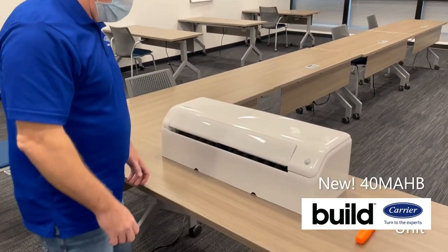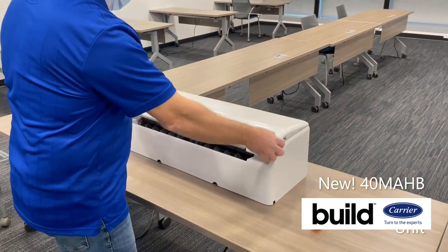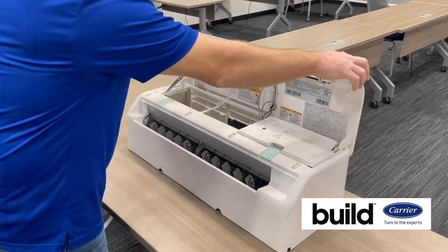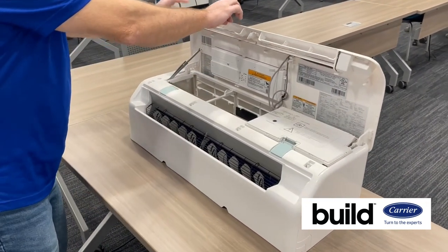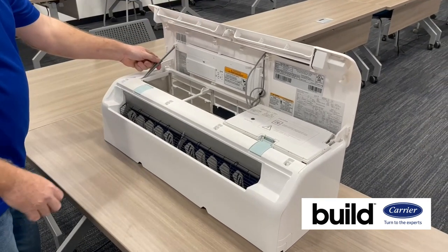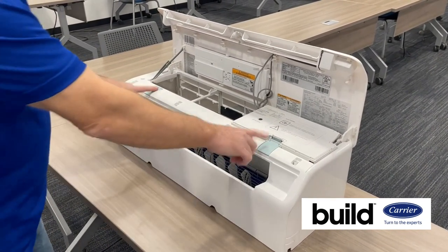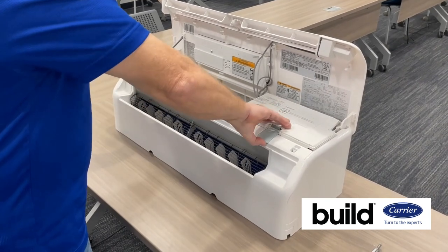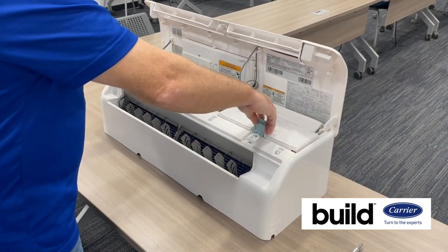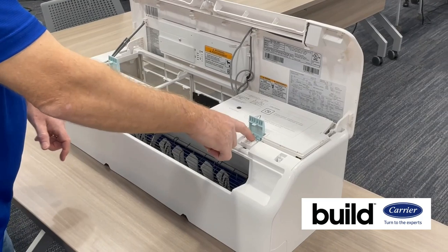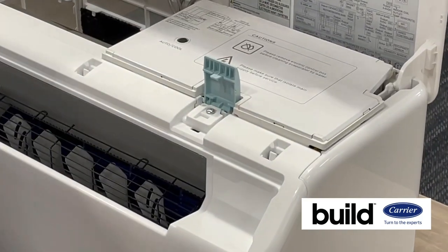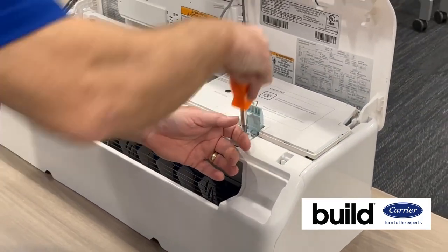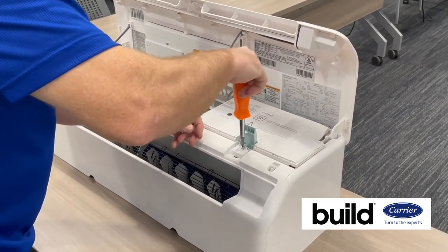Hi, this is just a quick video on how to disassemble the new Carrier mid-tier high wall unit. The first thing we want to do is hold it at each end, and then this prop rod, you position it all the way back and it will hold it up. Then you'll see you have two locking clasps right here and right here - all we want to do is take those loose, and there's just one screw holding this whole piece together, so with a Phillips head screwdriver you want to take that loose.